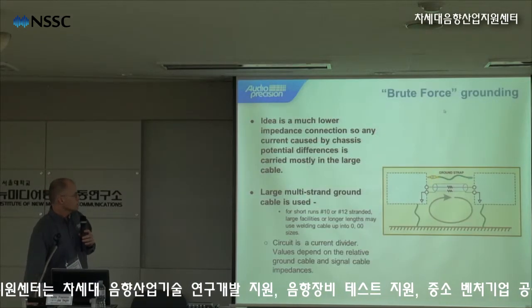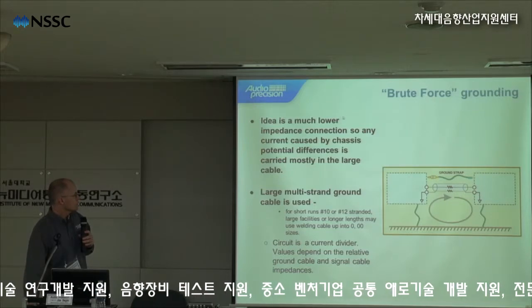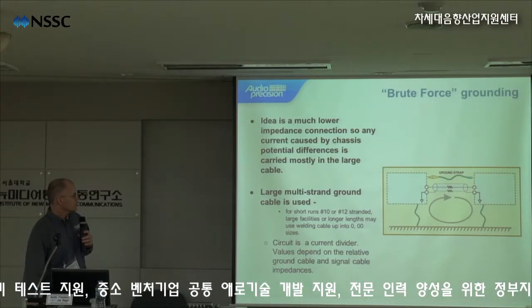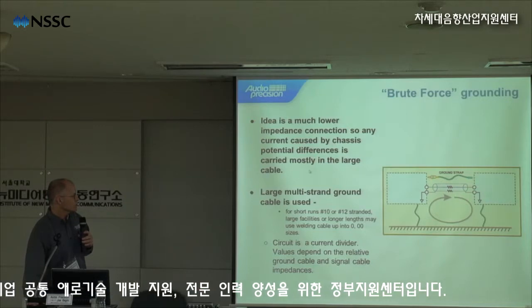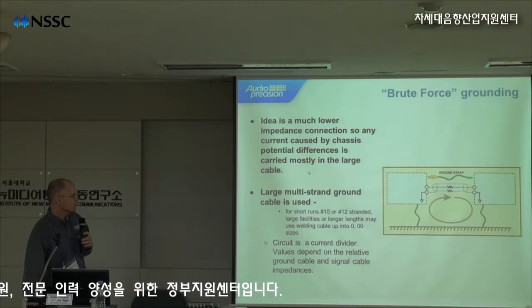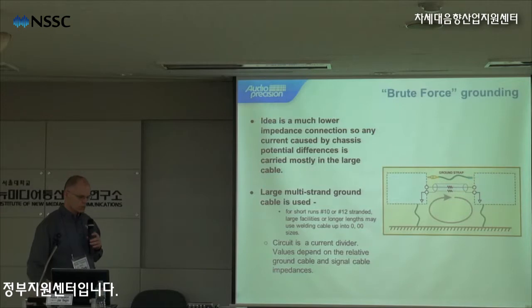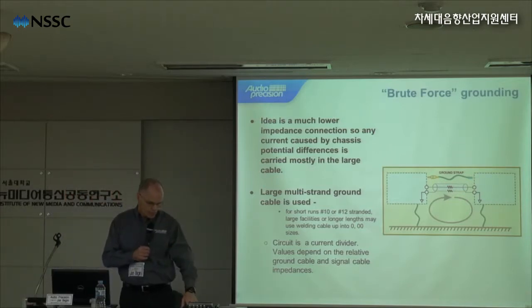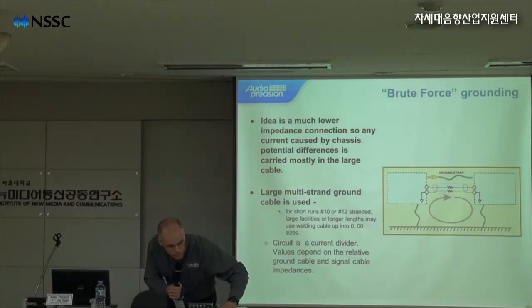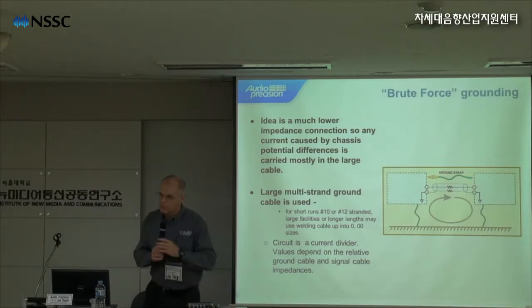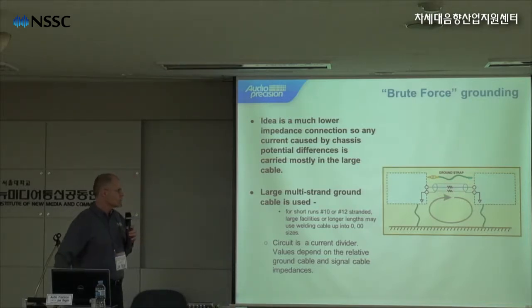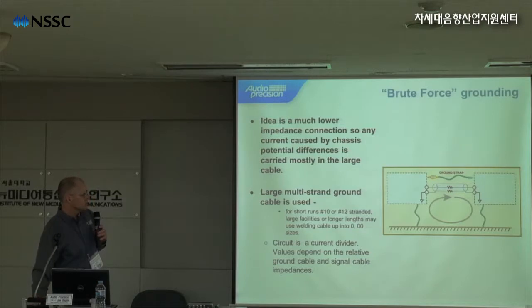So there's a technique called brute force grounding. The idea is to have a much lower impedance connection so that any current caused by the chassis potential differences is carried mostly in the cable. So you'll notice on our front panel and on the back panel of our analyzers we have these banana connectors that can be used to accept the ground terminal. It's also a screw lug. And the idea is you just use a large ground strap between the two pieces of equipment and ensure that the potential flows through that larger conductor.